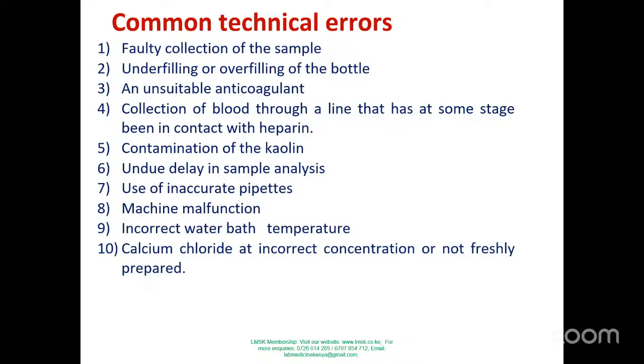The water bath has been lying there for maybe 5 years, 4 years. Nobody has ever cared to even contact the service providers to come and calibrate. And we are all happy that the water bath is at 37, when in real sense, the temperature there is at 24 or even 25. So you are not giving the right temperature for reaction.